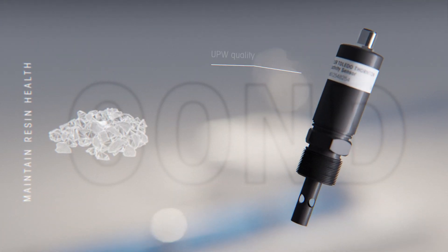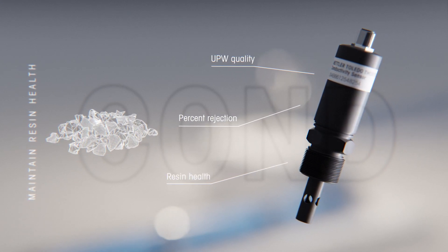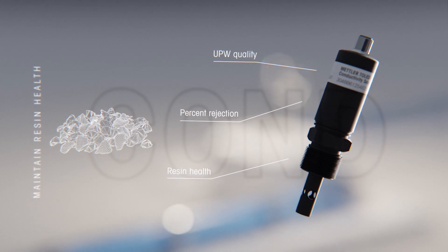In UPW generation, use resistivity sensors to monitor your ultra-pure water quality, percentage of rejection, and resin health to prevent waste and unnecessary resin replacement or maintenance.